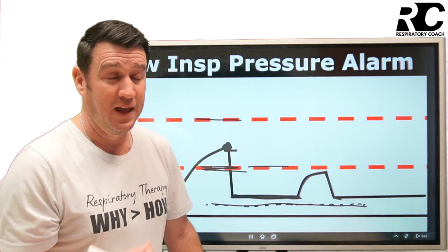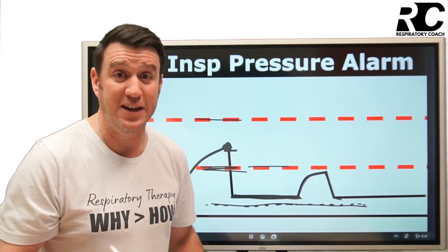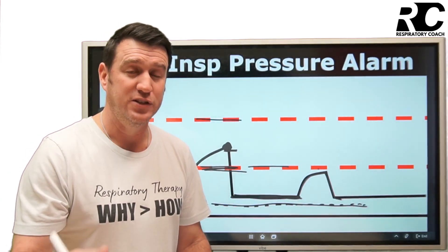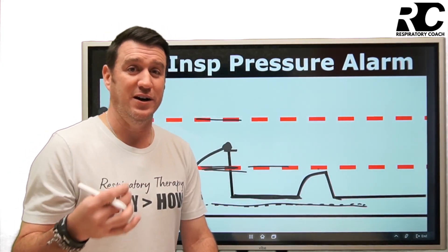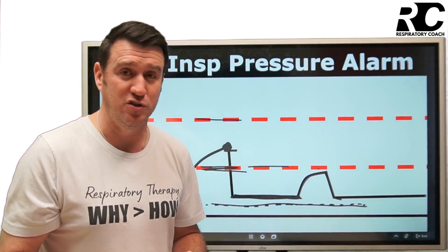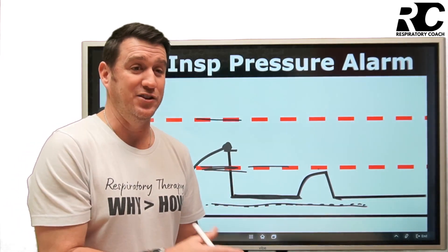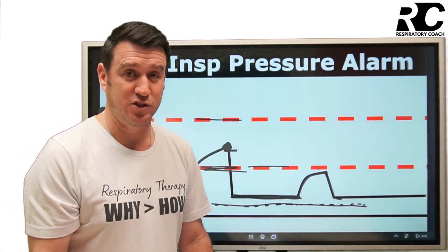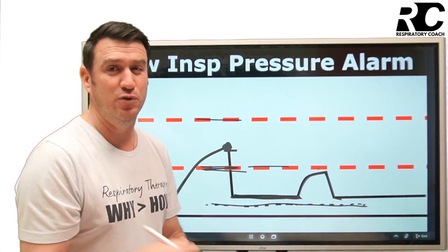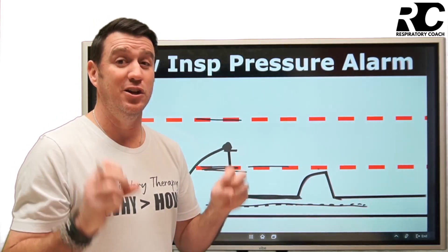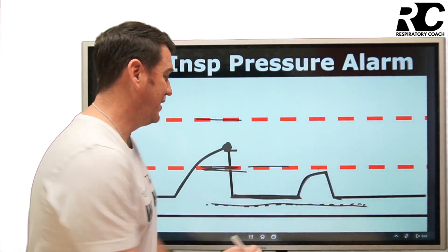Also keep in mind that a patient with a chest tube could potentially create a large leak. If you have a large pneumothorax with a chest tube inserted and you're getting a low pressure alarm, it may be related to that leak. So use the term 'leak' loosely when you're trying to identify the source.